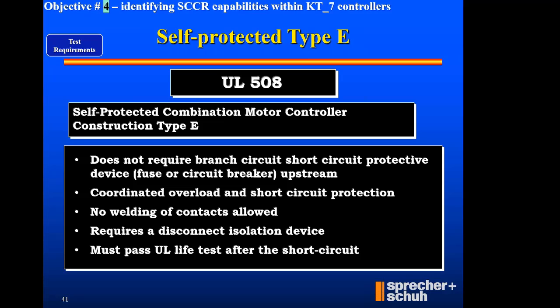What are the test requirements again for self-protected type E? Because under those charts, type 1 and type 2 was a type F kind of coordination. Here's what type E says. Type E says, hey, do not require branch circuit protection upstream because it's integrated already. Coordinated overload and short circuit protection? Well, that's already in the device. There shall be no welding of the contacts allowed from these test requirements. Requires a disconnect to where that's complied with. Here's the kicker for type E 508. Must pass a UL life test after the short circuit.